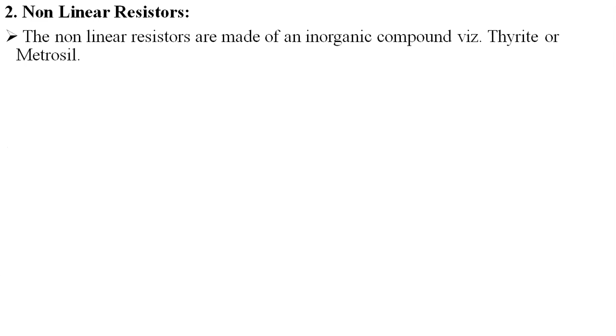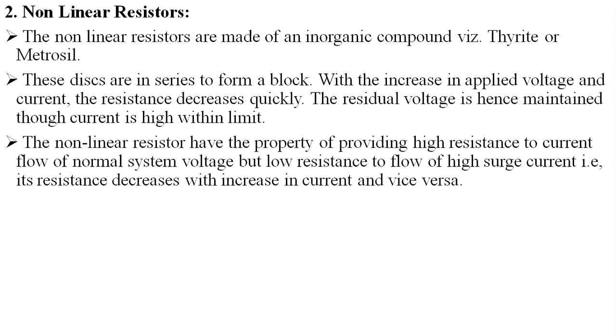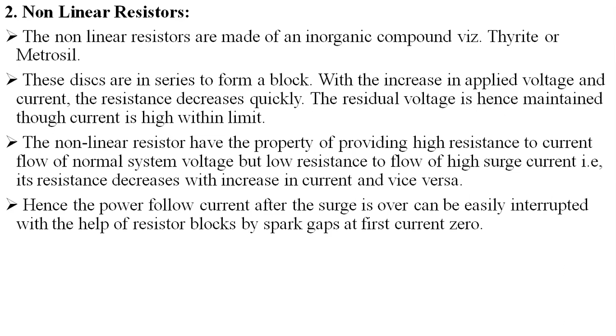Coming to the non-linear resistors. Non-linear resistors are made of an inorganic compound, thyrite or metrosil. These discs are in series to form a block. With the increase in applied voltage and current, the resistance decreases quickly, and the residual voltage is hence maintained even though the current is high, within the limit. The non-linear resistor has the property of providing high resistance to current flow at normal system voltage but low resistance to the flow of high surge current. That is, its resistance decreases with increase in the current and vice versa. Hence, the power follow current after the surge is over can be easily interrupted with the help of the resistor blocks and spark gaps at first current zero.